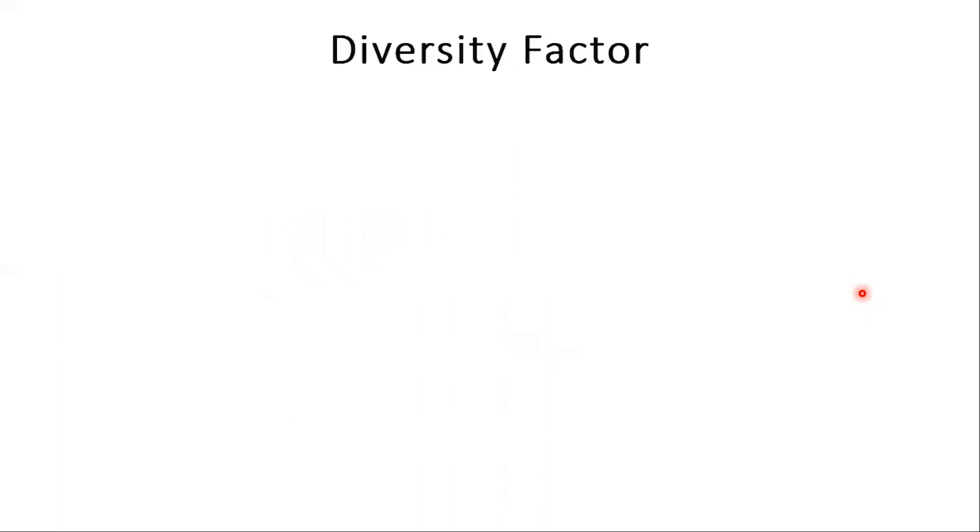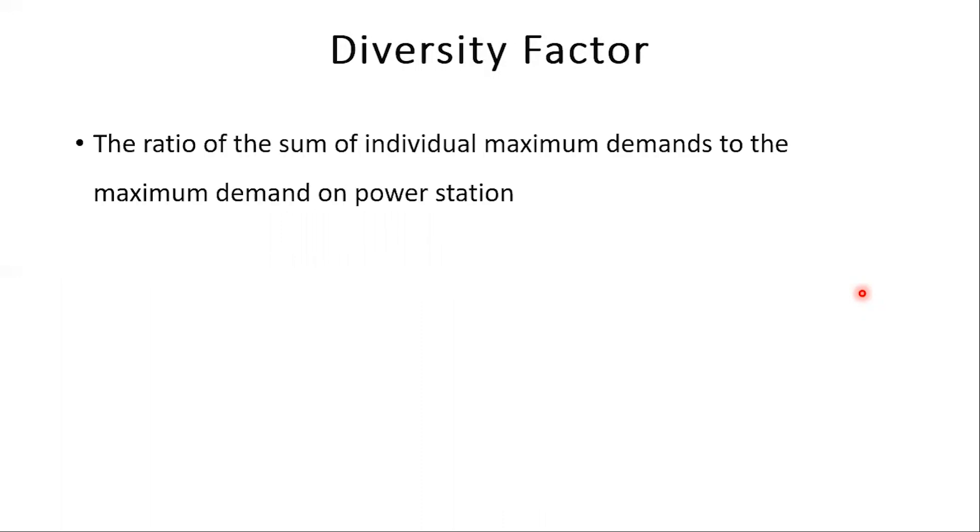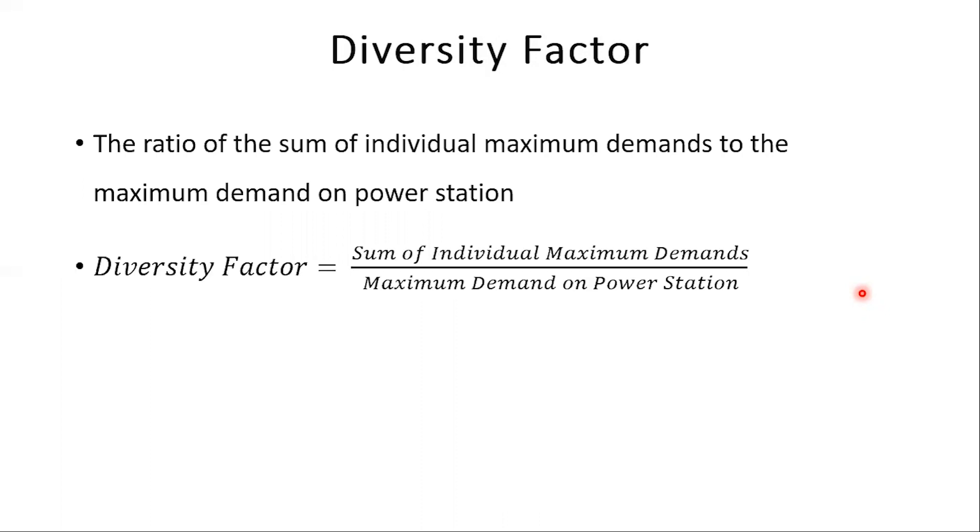Next on our theory is the diversity factor, which is the ratio of the sum of individual maximum demands to the maximum demand on the power station. You may have already observed that the diversity factor is defined for a system with multiple loads, while the load factor can be defined even for a single load.